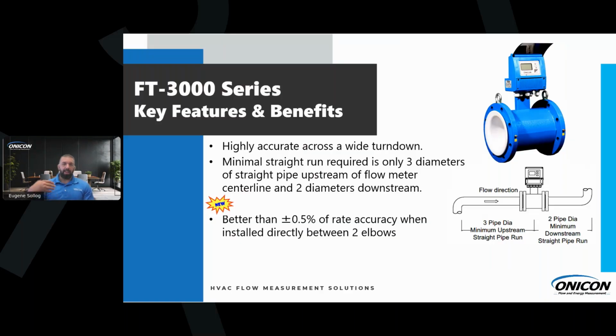Like I said, it's highly accurate across a wide turndown. This will go up to about 33 feet per second, as we'll look into when we deep dive into the transmitter. It also requires minimal straight run. To meet our accuracy statement, you only need 5 total pipe diameters: 3 upstream of the meter and 2 downstream. In the picture on the lower right-hand corner, it is measured from the center point of the flow meter. So even on the small flow meters, the meter body might be pretty close to your straight run requirements.